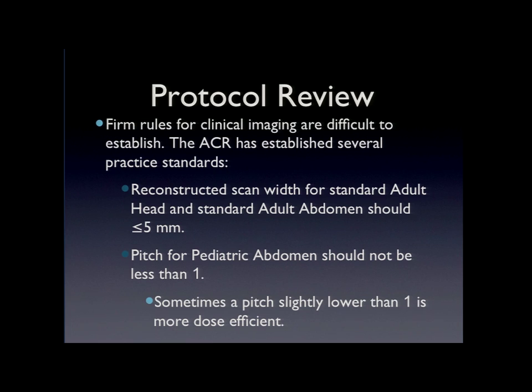The ACR has also given some guidance on the clinical end, recommending reconstructed scan widths for certain scanners and pitch for pediatric. Even though they have some recommendations, you just really need to evaluate. Sometimes you can go for a pitch less than 1, and the dose efficiency is actually more. So you need to look in real time at what the goal is, which is to get really good image quality while keeping the dose as low as we can.